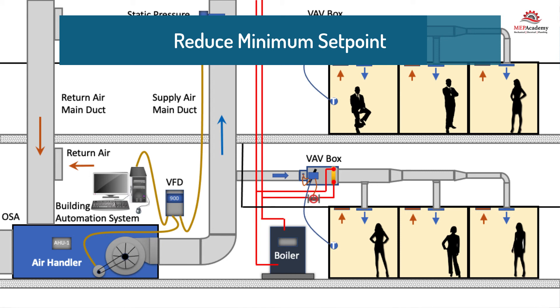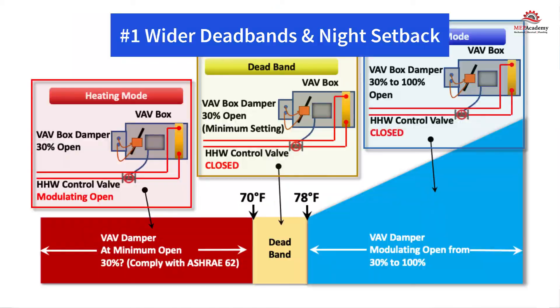This strategy will depend on the space type and usage. Number one: wider dead bands and night setbacks. On average, this was the number one way to save energy. The dead band is the temperature range when the HVAC system is neither calling for heating or cooling. By widening the dead band, the amount of time that the HVAC system saves energy increases. In California, zonal thermostats used to control both heating and cooling should be capable of providing a dead band of at least 5 degrees Fahrenheit.